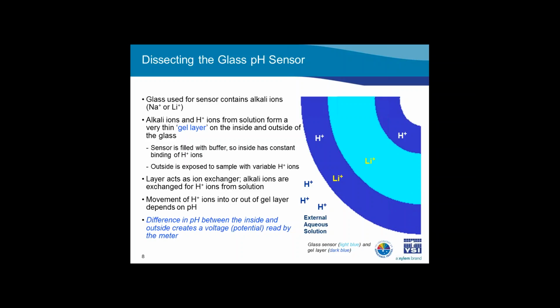With the pH electrode, the glass pH sensor, sometimes referred to as a membrane, is fused to an electrode shaft. The inside of the sensor is filled with the buffer solution of known pH, commonly pH 7. This electrode design creates an environment with constant binding of hydrogen ions on the inside of the glass sensor, while the outside of the glass is exposed to the sample, where a variable amount of hydrogen ions exist. The difference in pH creates a potential across the glass pH sensor that is compared to the stable potential of the reference electrode.